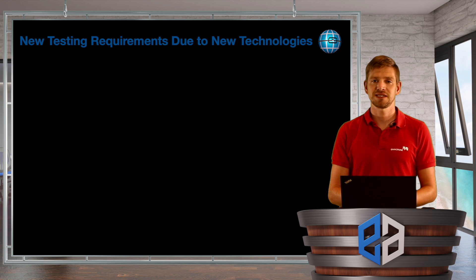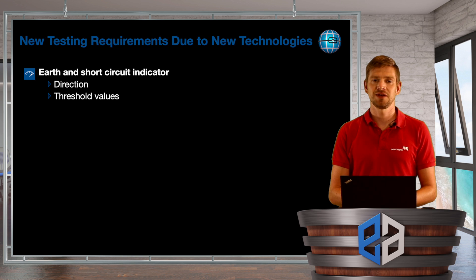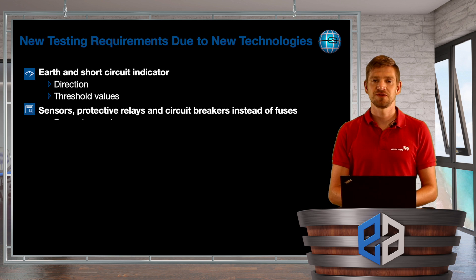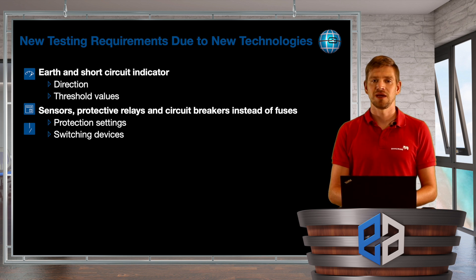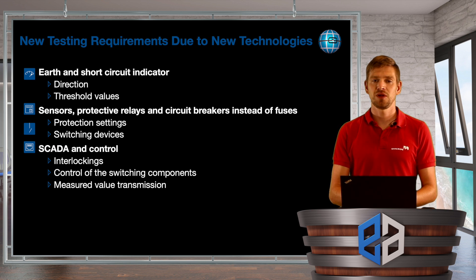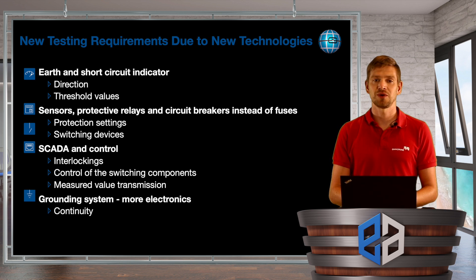What are the testing requirements due to the new technologies? For the earth and short circuit indicators we can test direction and threshold values. For the sensors, protection relays, and circuit breakers we can of course test the protection settings and the switching devices themselves with timing and for example contact resistance tests. For SCADA and control there can be interlocking and control of switching components, but measured values are also important. And as already mentioned, for the grounding system due to more electronics, we have continuity tests and grounding impedance measurements.